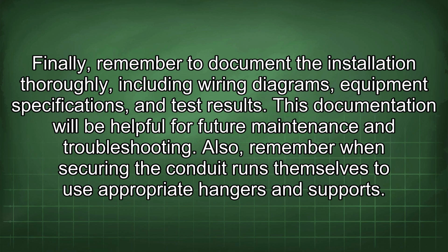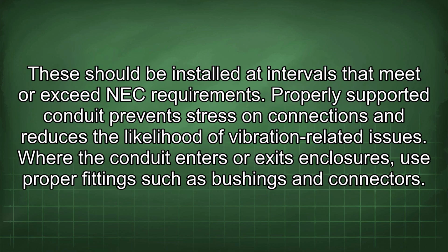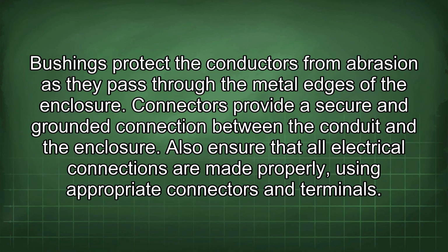Also, remember when securing the conduit runs themselves to use appropriate hangers and supports. These should be installed at intervals that meet or exceed NEC requirements. Properly supported conduit prevents stress on connections and reduces the likelihood of vibration-related issues. Where the conduit enters or exits enclosures, use proper fittings such as bushings and connectors. Bushings protect the conductors from abrasion as they pass through the metal edges of the enclosure. Connectors provide a secure and grounded connection between the conduit and the enclosure. Also ensure that all electrical connections are made properly, using appropriate connectors and terminals.